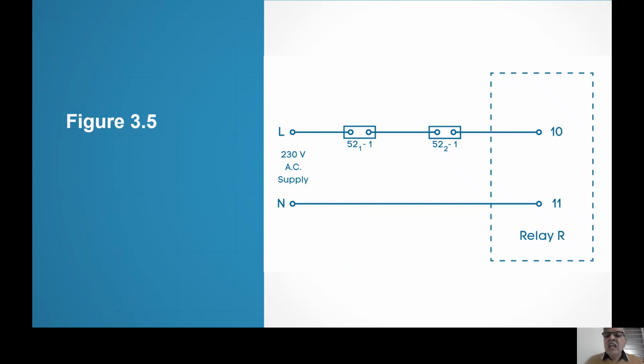Therefore, the NC auxiliary switches of breakers 52-1 and 52-2, that is 52-1-1 and 52-2-1, can be wired to feed the binary input. Automatically the setting will change at night. No doubt that setting you will have to configure in advance. That is true. But that will come into the picture, and that you will be using, right? So that is very important about this relay.